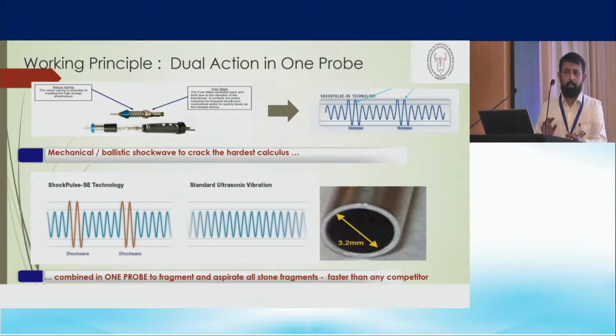Again, the important thing is that along with the fragmentation, the probe they have made has a very large channel, up to around 3.2 millimeters. So that can suck the fragments up to around 8 to 9 millimeters. Larger fragments can be sucked very easily with this probe. That is the advantage. Even the Trilogy has a still slightly bigger lumen size compared to the shock pulse.